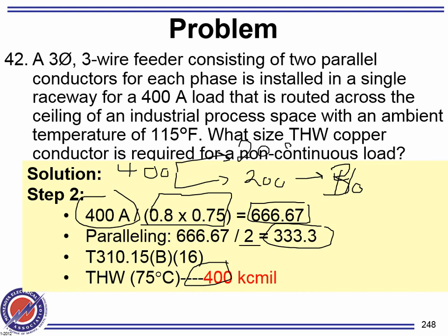Yeah, it'll be cheaper to do that. We have like 6 of them at 400 kcmil. You might be able to put it in 4 inch EMT now. 6 of them are tight. It's the dumbest thing they can do. It's not just tight. If less ground, it'll be very tight. When the size is that large, guys, separate conduit. That's the easiest way to do it.